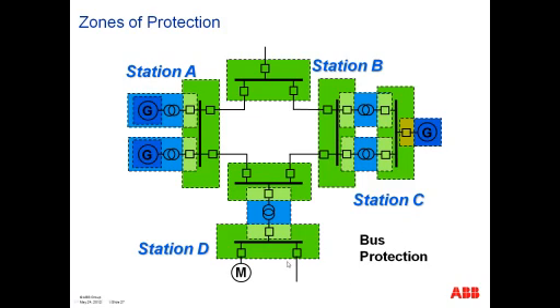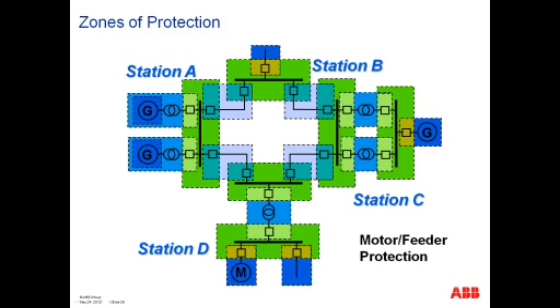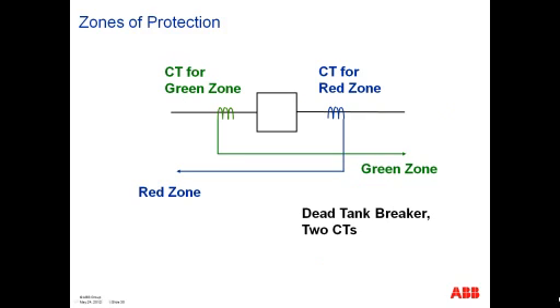Here we begin looking at the bus and the overlapping zones. But here is shown the bus protection that these are connected to. And then, of course, the next one would be the line protection, as shown there. And as you see in all these illustrations, of the overlapping that exists between the zones, the common breakers that exist. Okay, and finally the load.